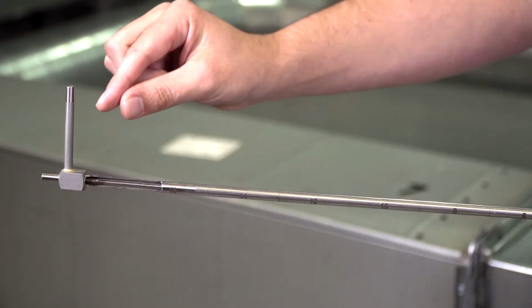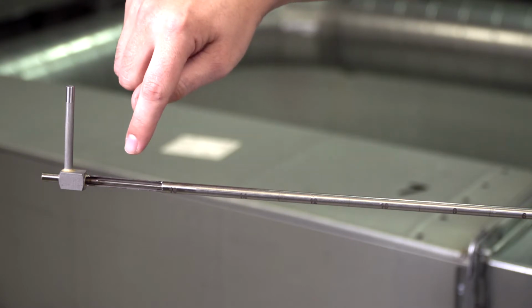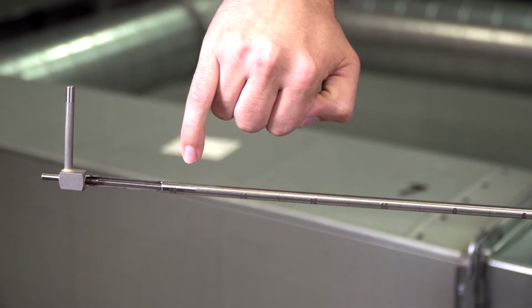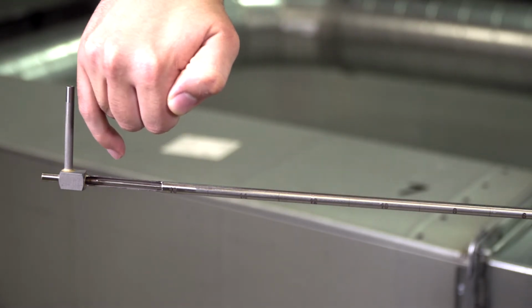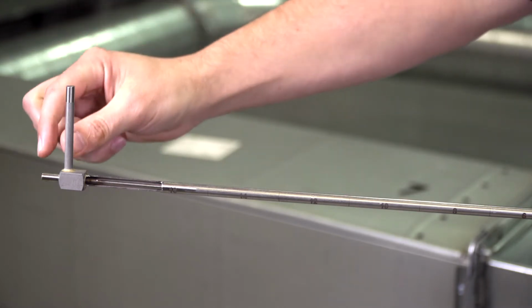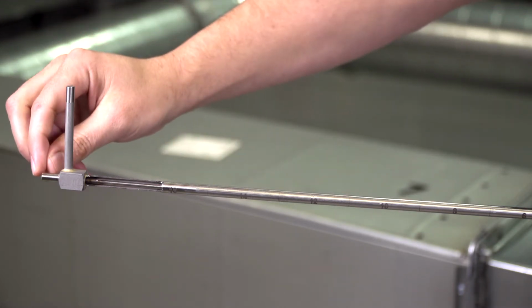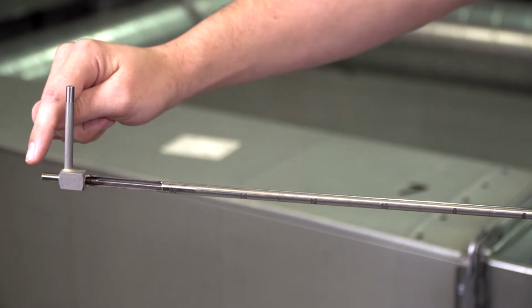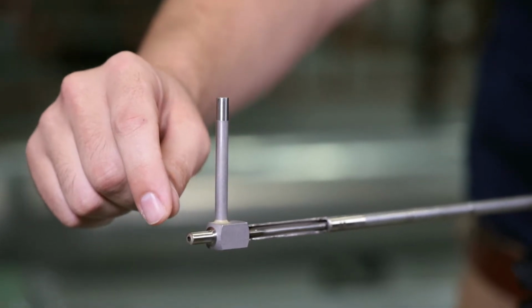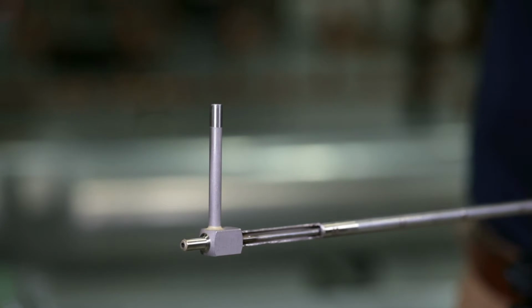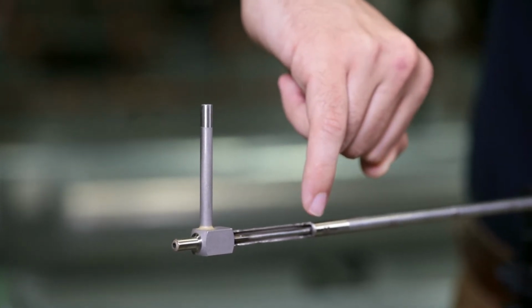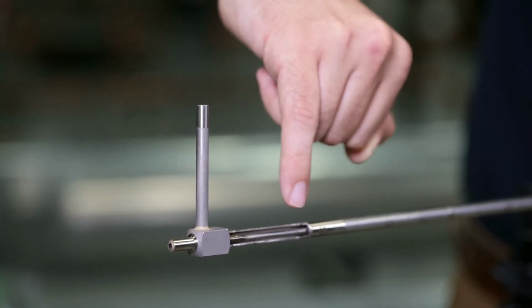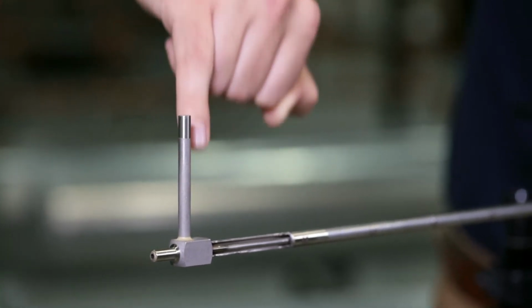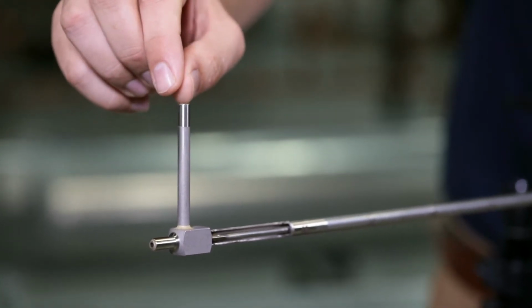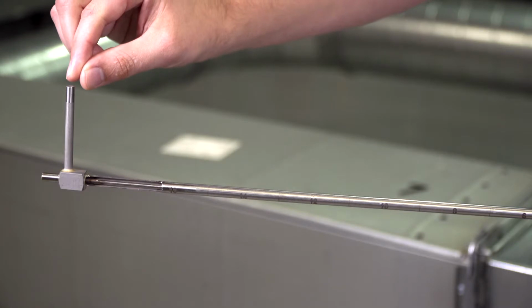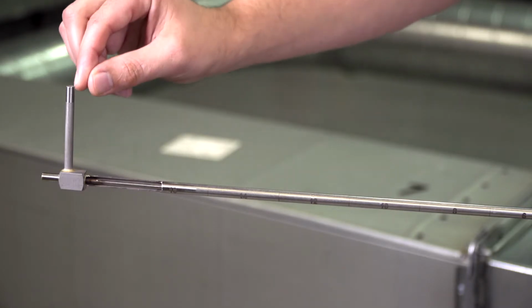At this end of the pitot tube, we again have our cutaway, where the inner tube is the total pressure tube, and it is connected to this port at the end. This port is typically connected to the high side of the manometer. The radial outer tube runs to this port, and this is typically connected to the low side of the manometer.